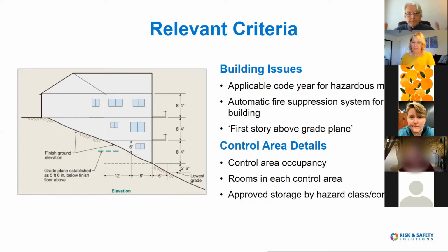Because you bring a new bottle of something flammable or toxic into your building, that's an ongoing use. Is that Title 19 that takes over? Which code year do I apply? And it is a challenge. Older buildings are not built for modern MAQ codes. We have buildings in the UC system that were built in the 1800s. And so, what code year you apply is a prescient question, and it requires people that both understand the construction and the intent of the code to be able to answer that. But in our software development, we give the options to the people that are the fire authorities to pick the code year.